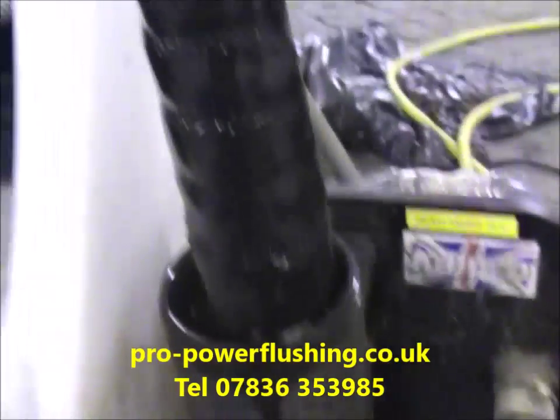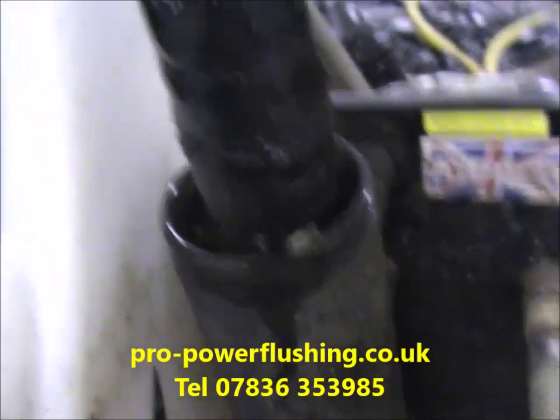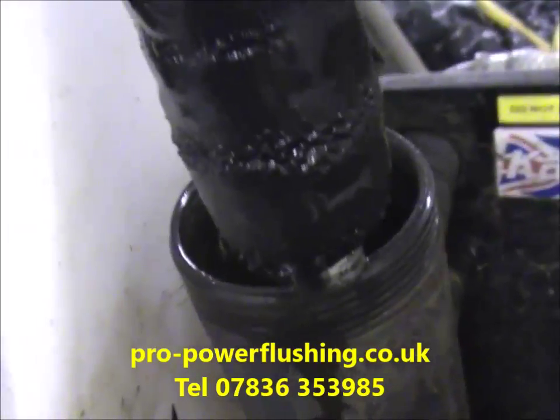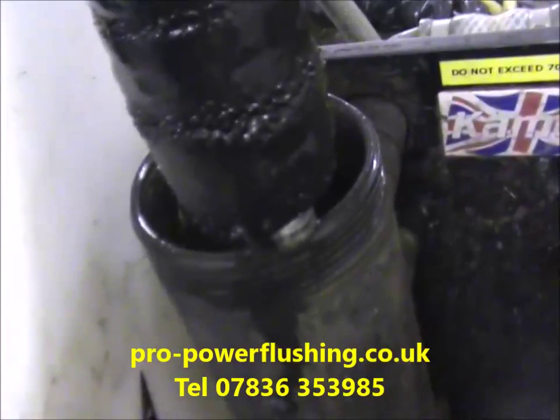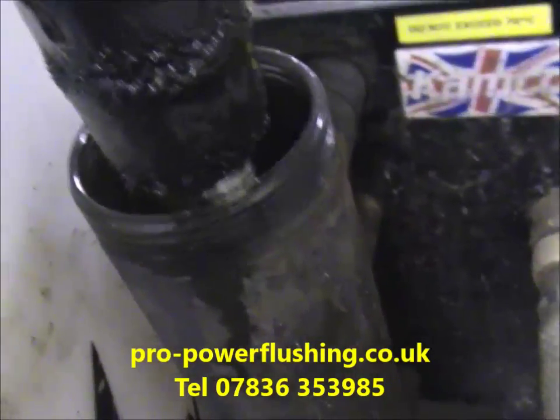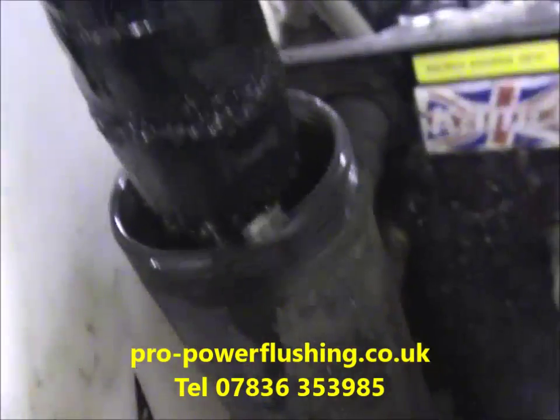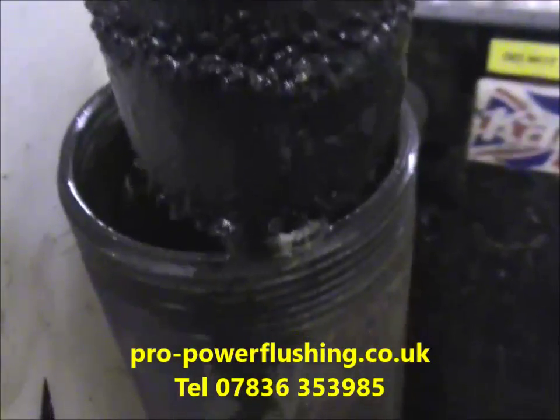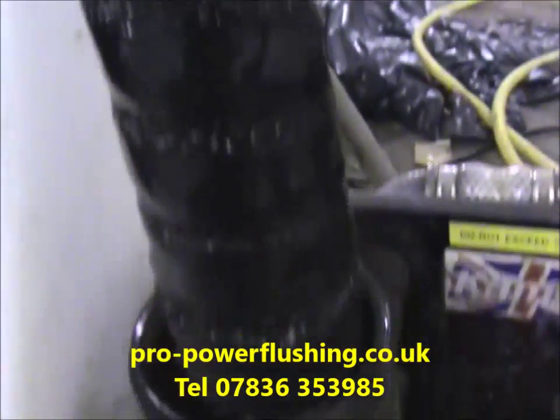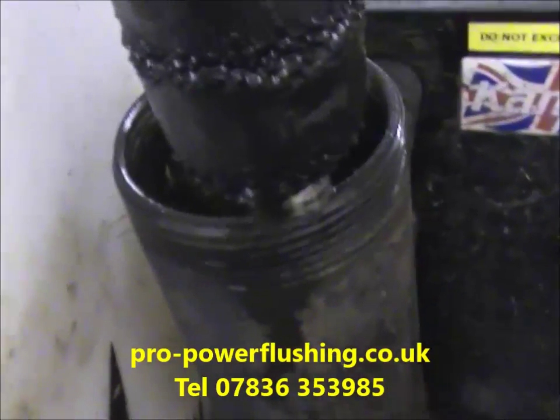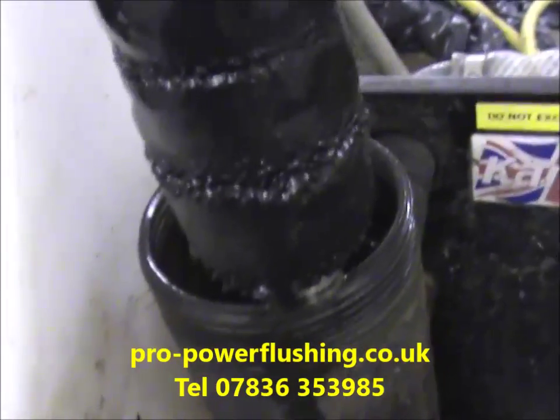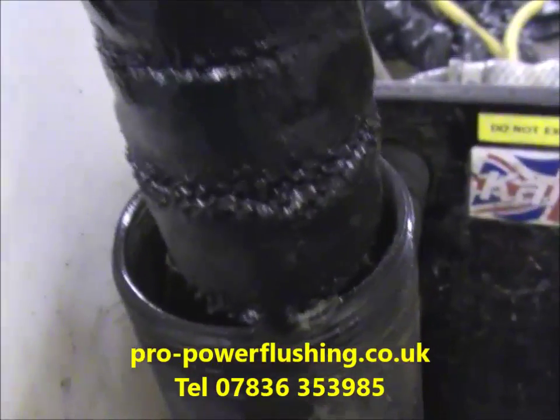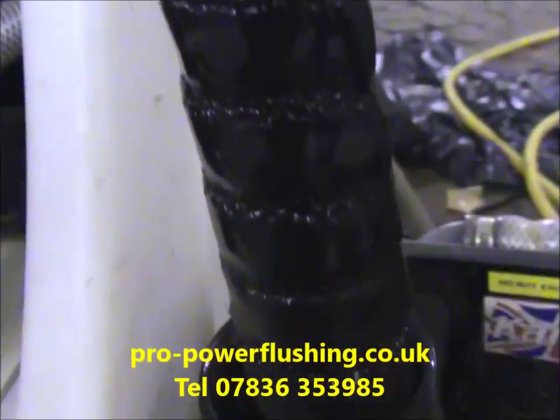Now this is quite a large system, about 30 radiators in this property, and this is the metal and rust and corrosion that's coming out of the central heating system. That's what destroys pumps, blocks diverter valves up, and generally causes mayhem in your central heating system. This is what powerflushing is all about. There's some fairly big pieces in there, so this system will be running a lot better. Now we're getting all this rust and corrosion out of the central heating system. It's going okay, so we'll just get back to you later.